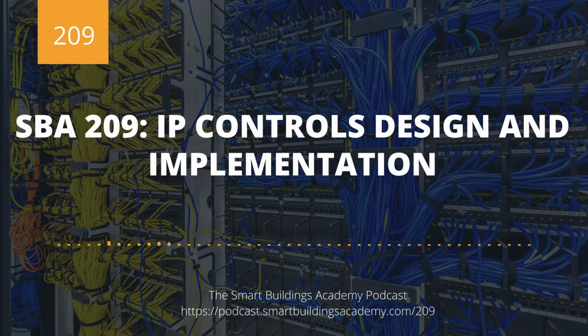There's really three design aspects of IP controls, and those are star, bus, and ring. Star is basically point-to-point IP addressing. The benefit of it is that if a controller goes down, you only lose that controller. And that'll be important when we start talking about bus and ring architectures. The downside of it, though, is that it takes up a dedicated switch port on a switch.